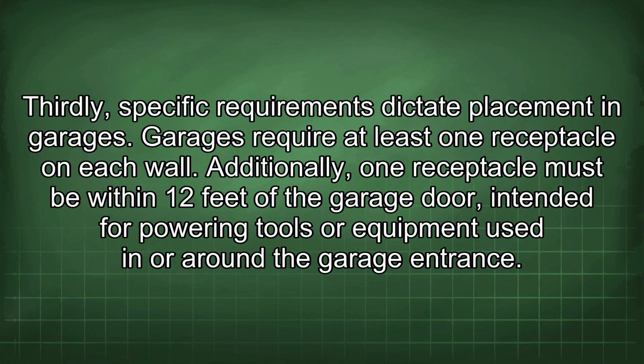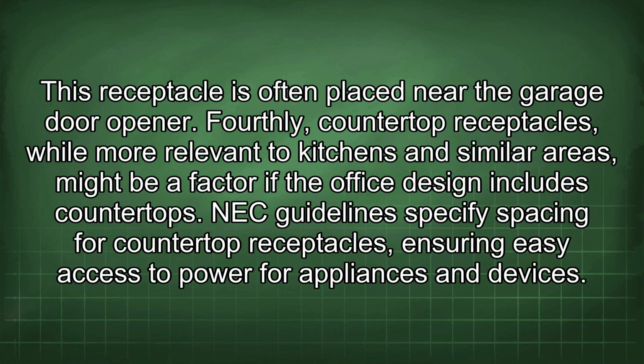Thirdly, specific requirements dictate placement in garages. Garages require at least one receptacle on each wall. Additionally, one receptacle must be within 12 feet of the garage door, intended for powering tools or equipment used in or around the garage entrance. This receptacle is often placed near the garage door opener. Fourthly, countertop receptacles, while more relevant to kitchens and similar areas, might be a factor if the office design includes countertops. NEC guidelines specify spacing for countertop receptacles, ensuring easy access to power for appliances and devices.